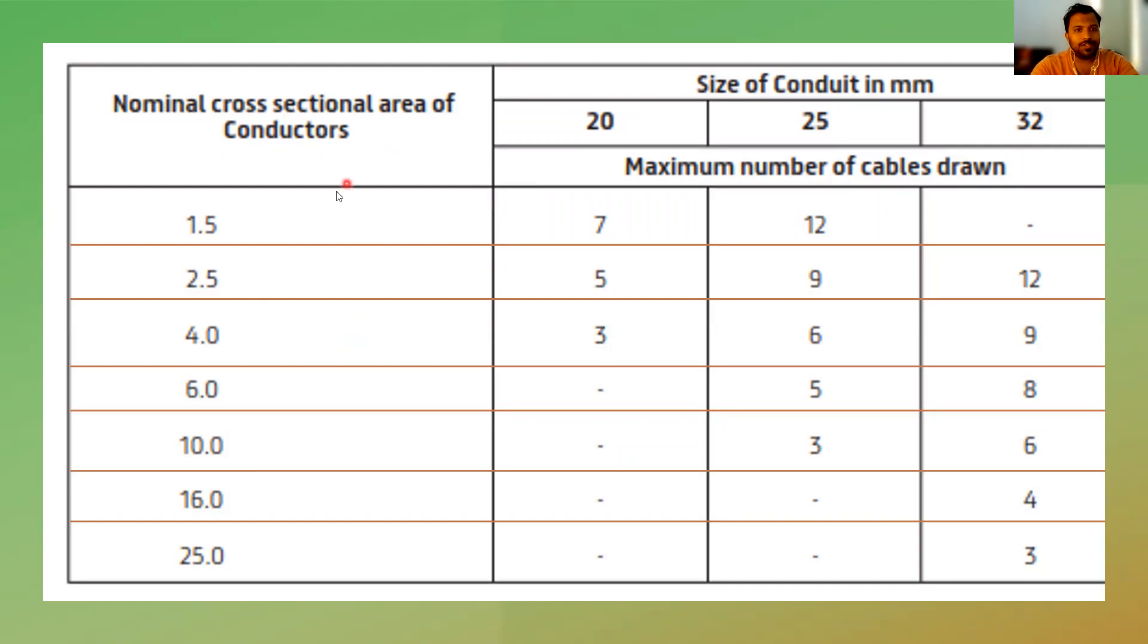So here in this chart, you will see the nominal cross-sectional area of single core wires, 1.5 to 25 mm, in the 20, 25, 32 mm conduit sections. So in the 20 mm conduit, what is the limitation? In 20 mm conduit, you can draw 7 number of wires.